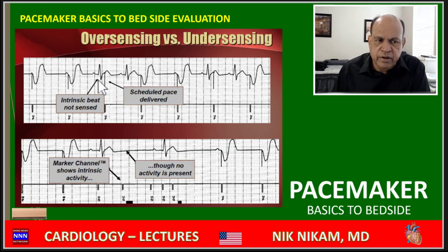Initially it sensed the normal beat, but somehow later on it just came and delivered an electrical impulse, which is not appropriate because it is not sensing this PQRS complex in an appropriate manner as it is set to recognize. Similarly, we have a pace beat, and we have the same issue here. So this is improper sensing.